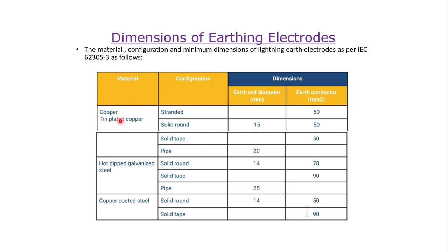For material copper or tin-plated copper: if the configuration is stranded, the earthing conductor size would be 50 square mm. If it is solid round, the earth rod diameter would be 15 mm and the earth conductor is 50 square mm. If it is solid tape, the earth conductor size would also be 50 square mm.